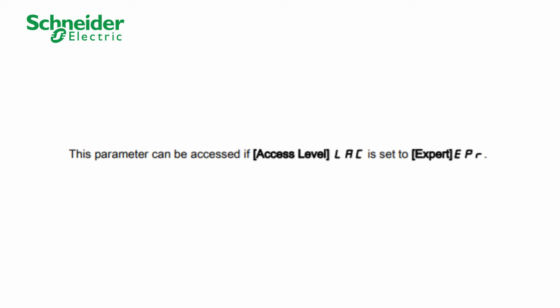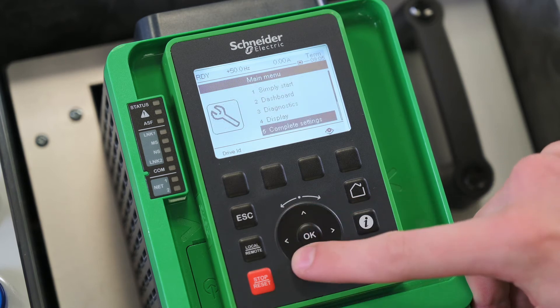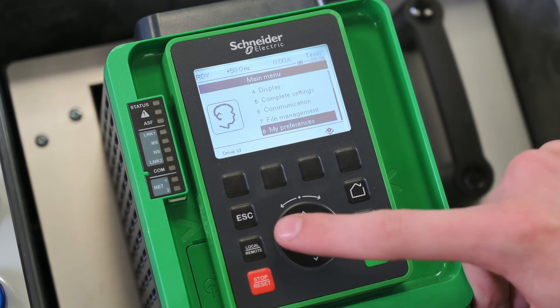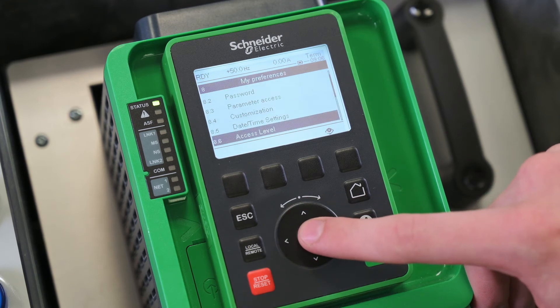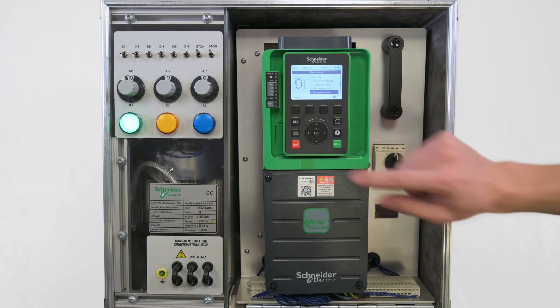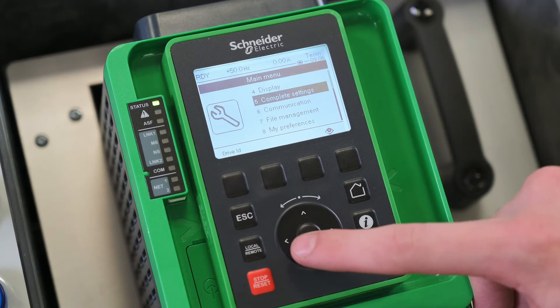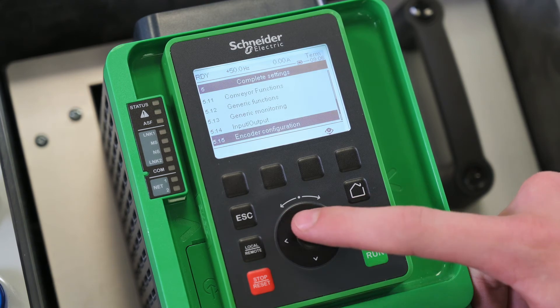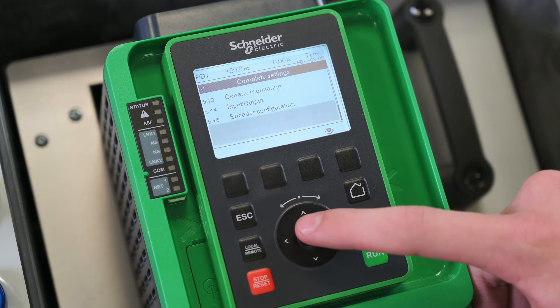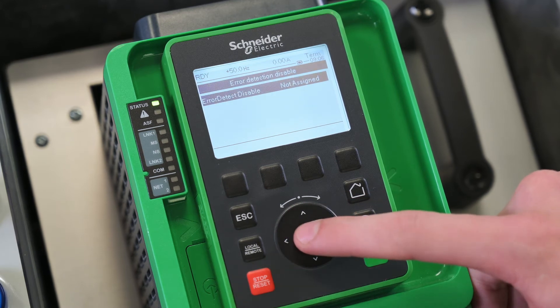Firstly, we are going to set the drive access level to Expert. Then, we are going to assign the error detection disable parameter to a digital input, here DI5. Navigate to Complete settings, then Error warning handling, then Error detection disable.